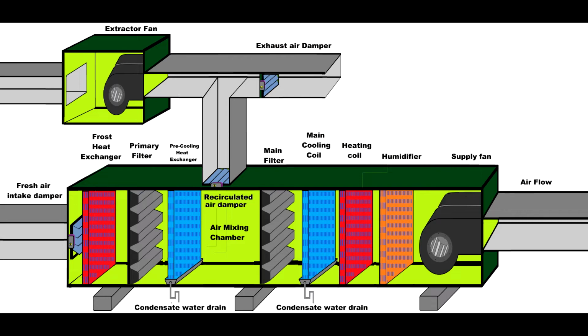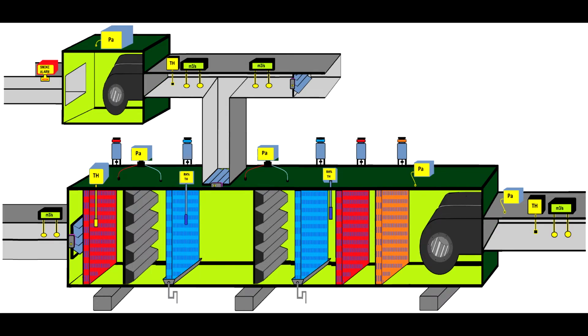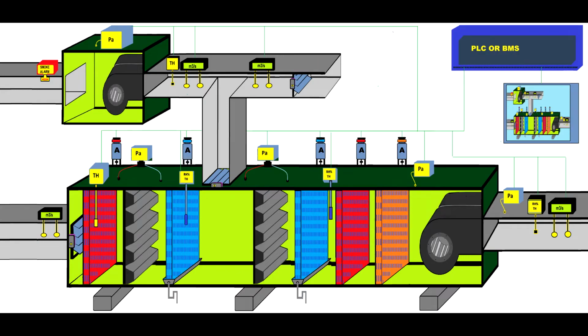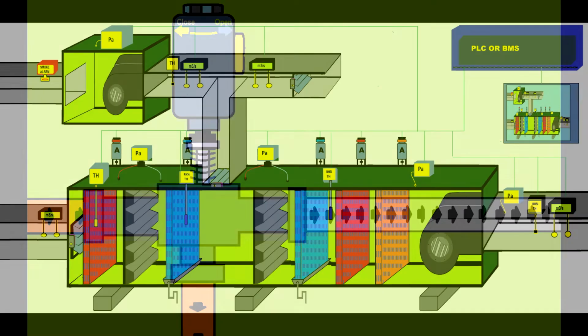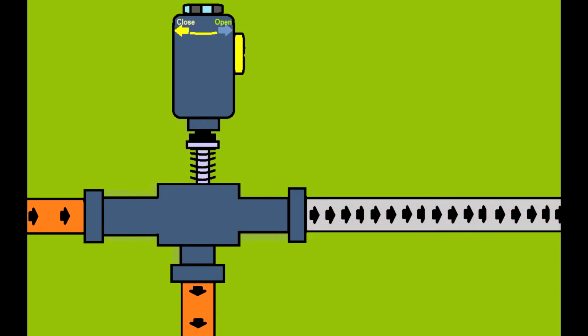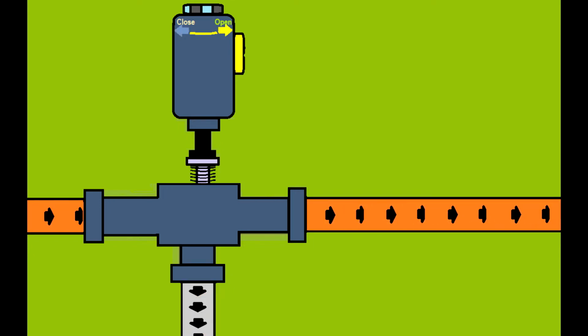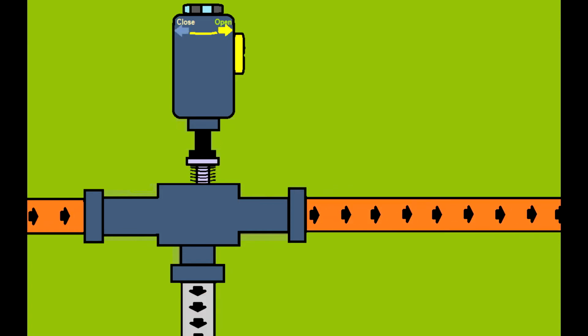All these things need to be controlled by something. That's why we use actuators, velocity probes, differential pressure switches. And what controls this? A programmable logic controller, and you can see it on an HMI. All these heat exchangers are controlled by actuators. Like you see here, the actuator has the capability to divert the flow. This is a hot agent which will pass through a valve, and the valve will direct the flow to a heat exchanger, or it will recirculate the flow if the temperature is satisfied.